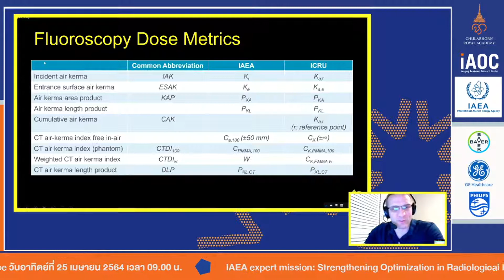So there's a variety of different metrics. What we're going to focus on today for traditional real-time fluoroscopy is the KAP, or the Kerma area product, the cumulative air Kerma, and this is with respect to the reference point, which I'll talk about, peak skin dose, and fluoroscopy time. And then there's the fluoroscopy C-arm on interventional systems and even some mobile C-arms, which can actually spin in a programmed way to create a volumetric CT data set. In that case, there are a variety of different metrics we'll talk about, and we'll get to that at the end of the talk.